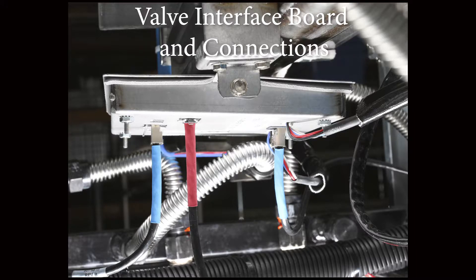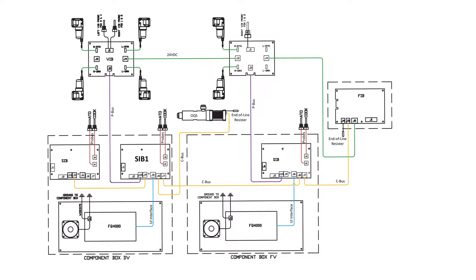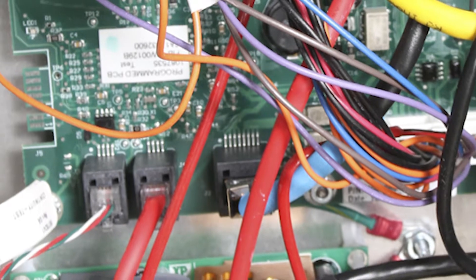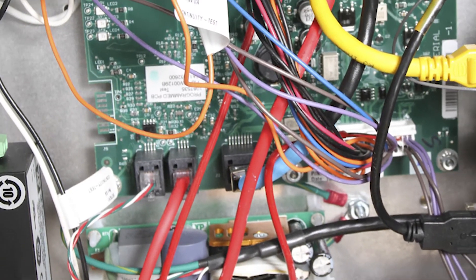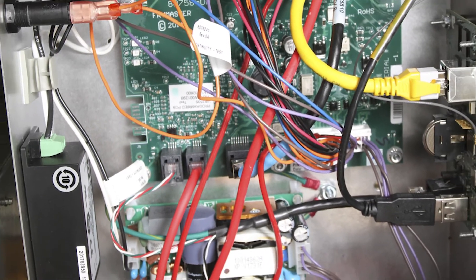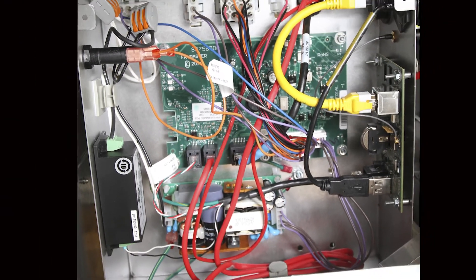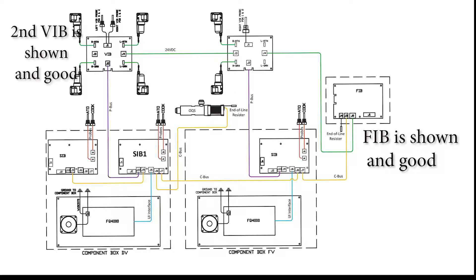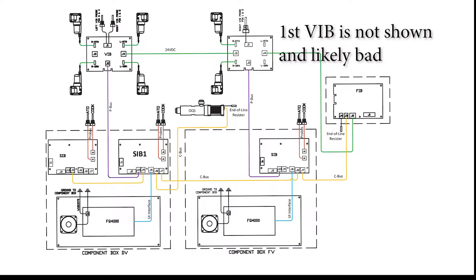The problem can be the harness between the boards or the connection between the harness and the board. A board with missing revision data that's between visible boards on the wiring sequence is likely bad.